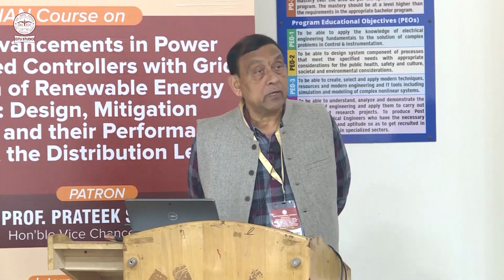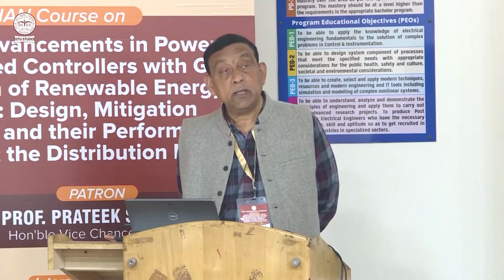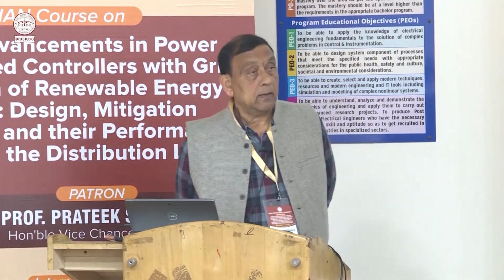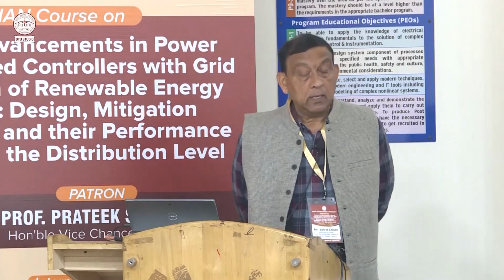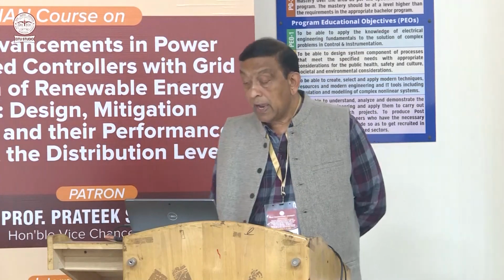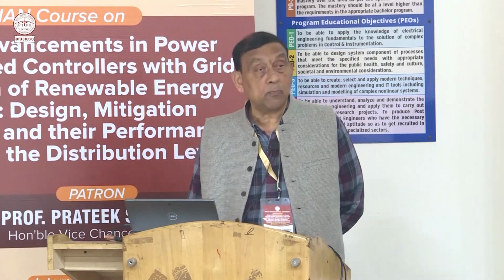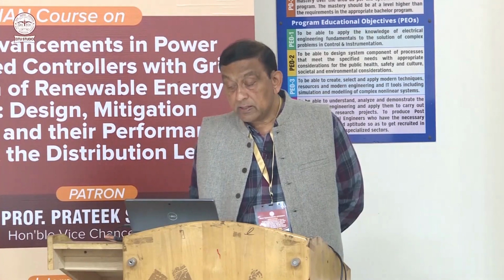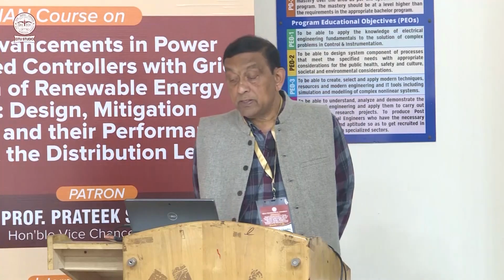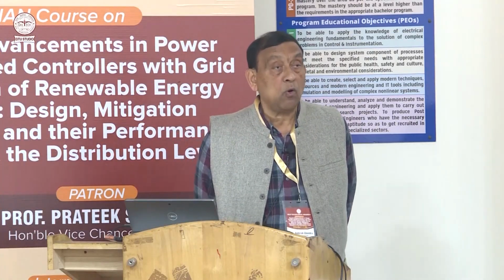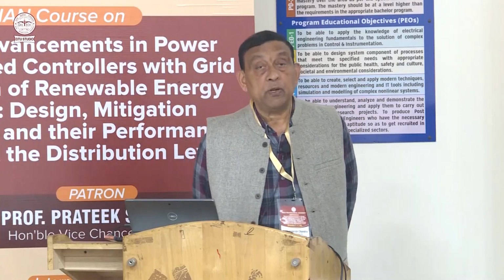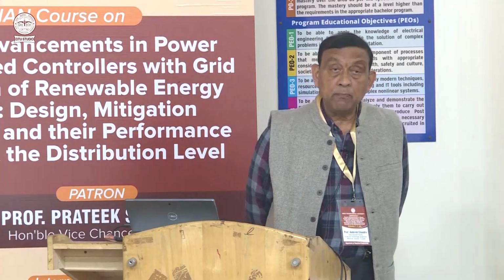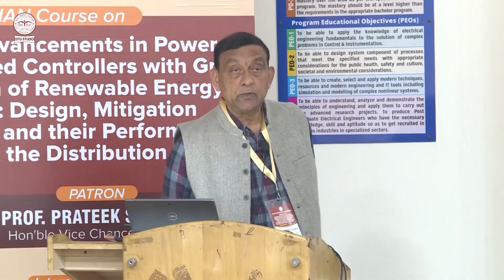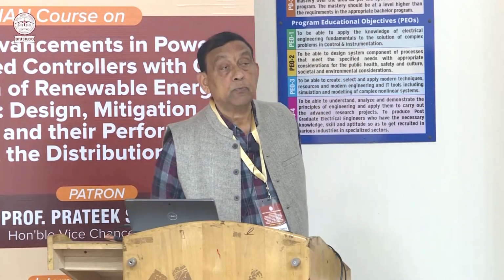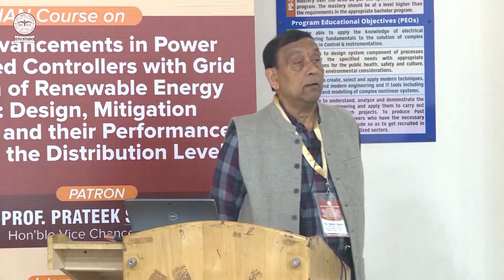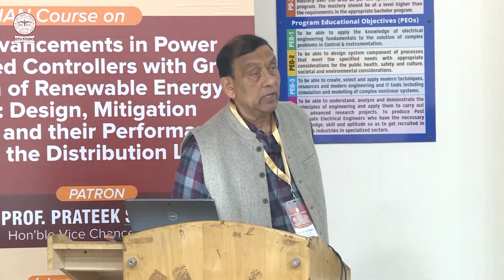Then degradation and considerable reduction of capacitor life. A capacitor may attract higher harmonics because its reactance decreases with frequency. Then voltage distortion, heating and torque pulsation in motors. We discussed how the fundamental frequency generates a rotating magnetic field in the air gap between stator and rotor, a stable torque is produced, and the rotor rotates in the same direction as the rotating magnetic field.